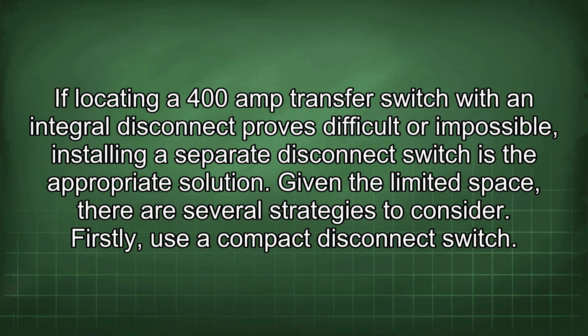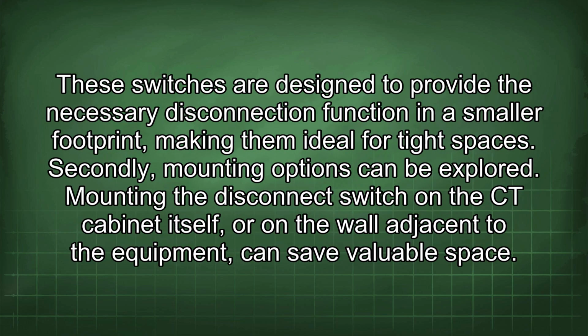If locating a 400 amp transfer switch with an integral disconnect proves difficult or impossible, installing a separate disconnect switch is the appropriate solution. Given the limited space, there are several strategies to consider. Firstly, use a compact disconnect switch. These switches are designed to provide the necessary disconnection function in a smaller footprint, making them ideal for tight spaces.